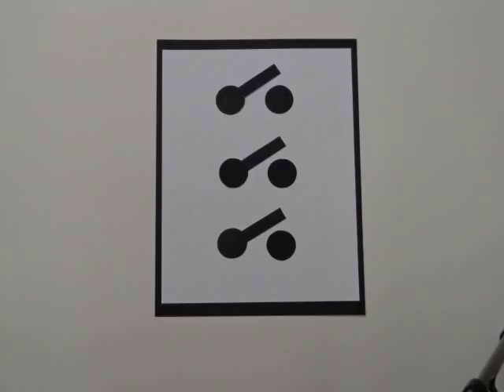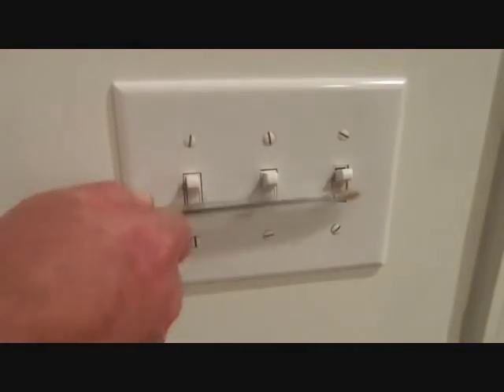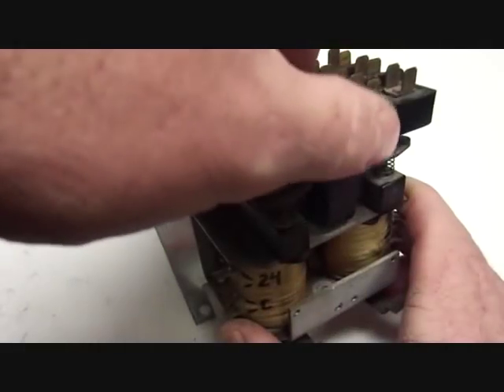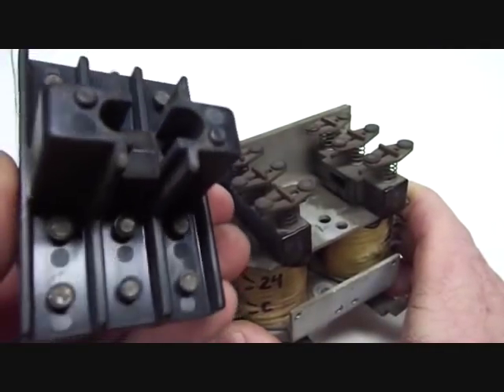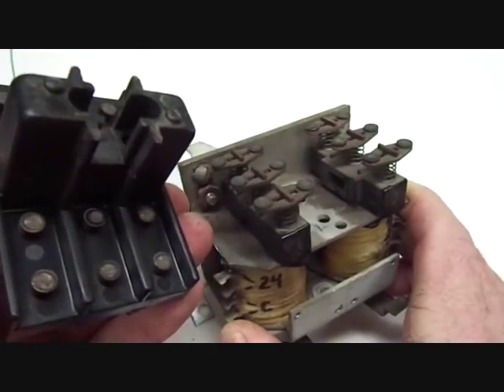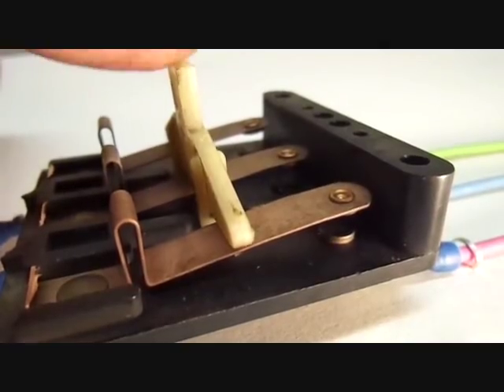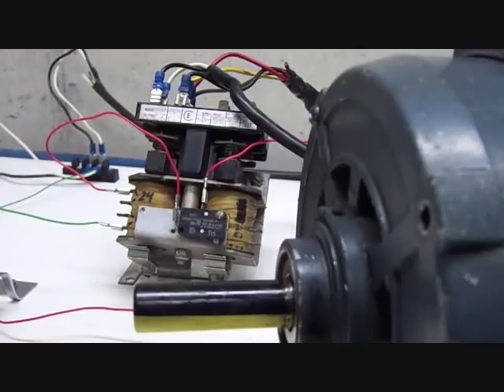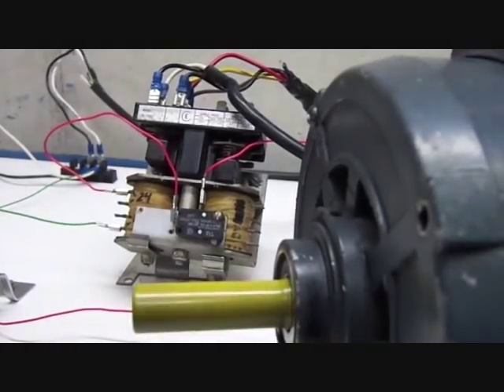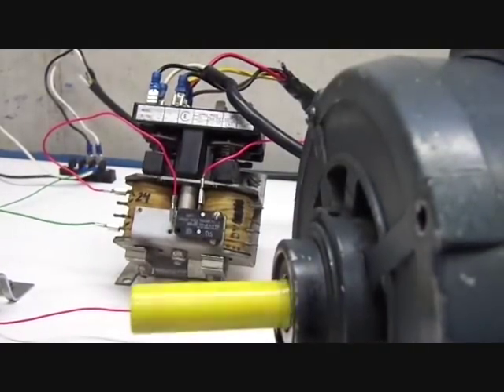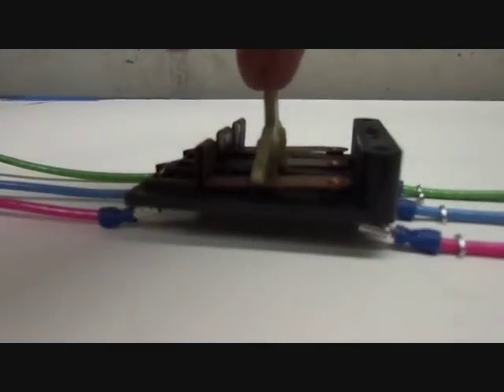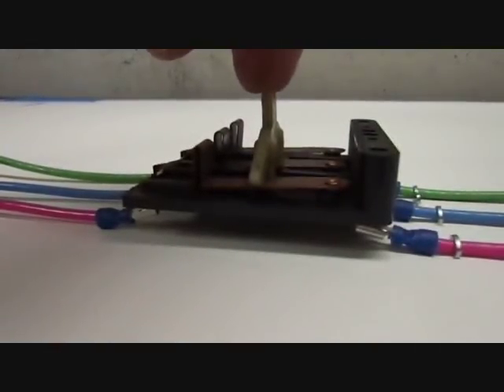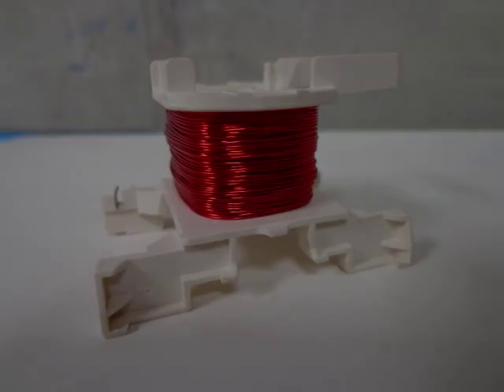This one has three poles. It's like having three separate switches that are all activated by that 24-volt coil. These poles are all independent of each other, so you could use them for three separate circuits with three totally different voltages. But most of the time, they're all used together to run a single motor. And any voltage you send through the main contacts is going to be isolated from the coil, so you don't have to worry about the high-voltage mixing with the low-voltage circuit.